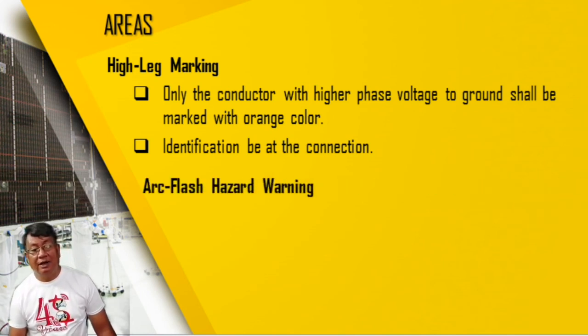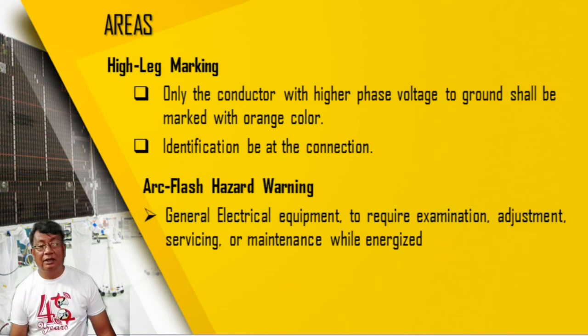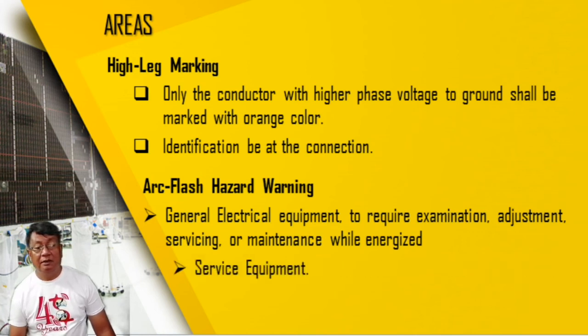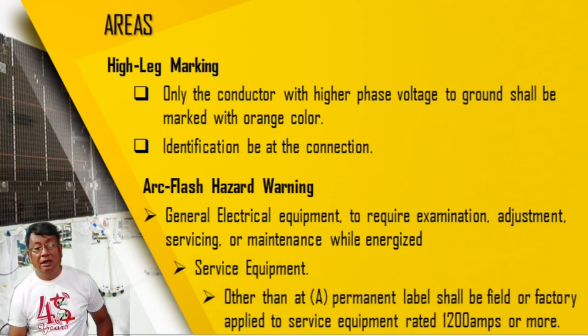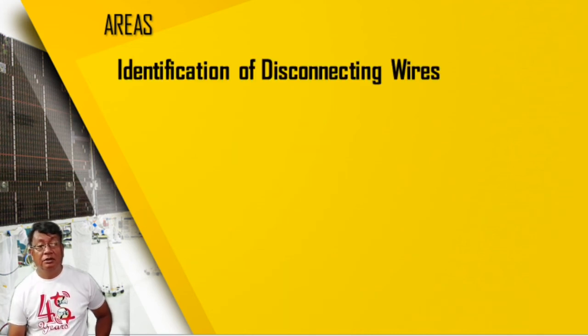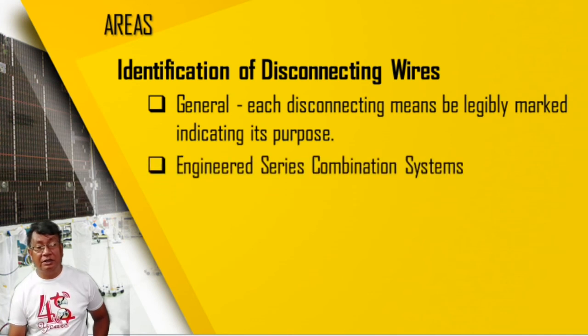Okay, so arc flash hazard warning. General electrical equipment that requires examination, adjustment, servicing, or maintenance while energized. Okay, service equipment other than dwelling units: a permanent label shall be field or factory applied to service equipment rated 1,200 amperes or more. Okay, so identification of disconnecting means. In general, disconnecting means shall be legibly marked indicating its purpose.